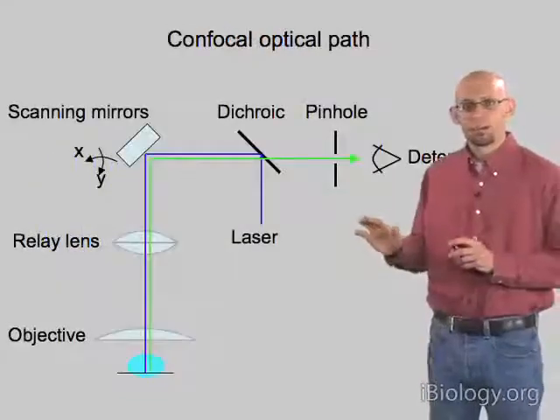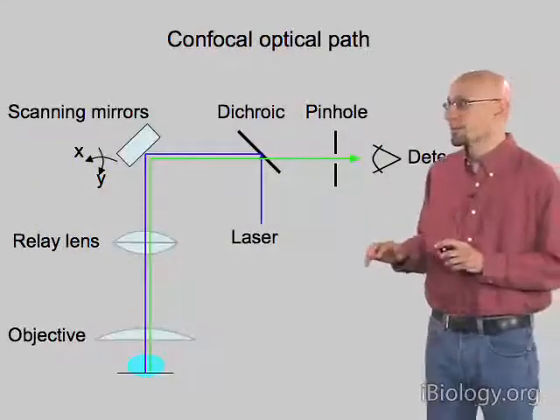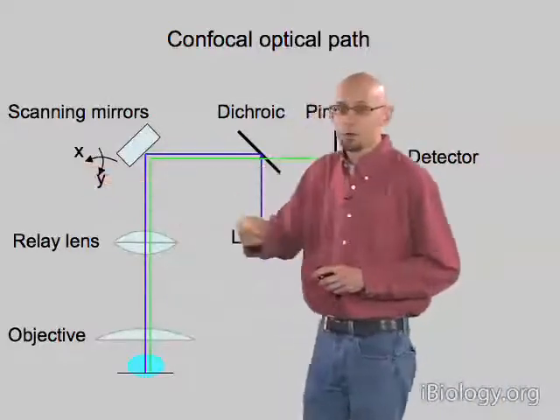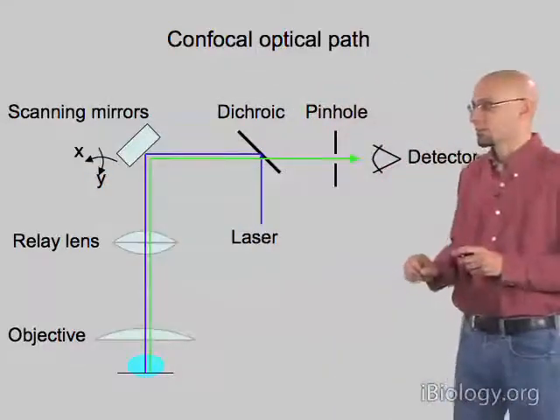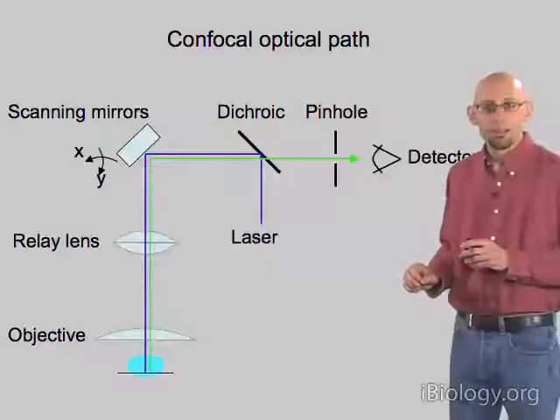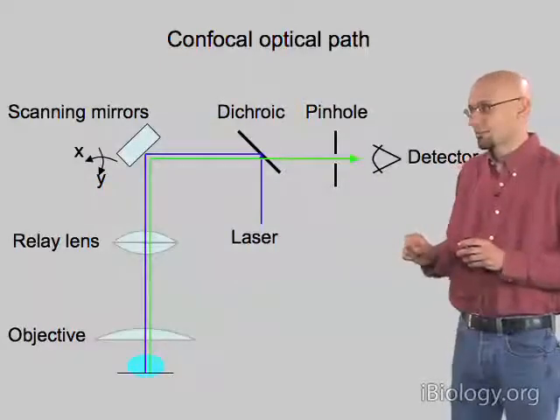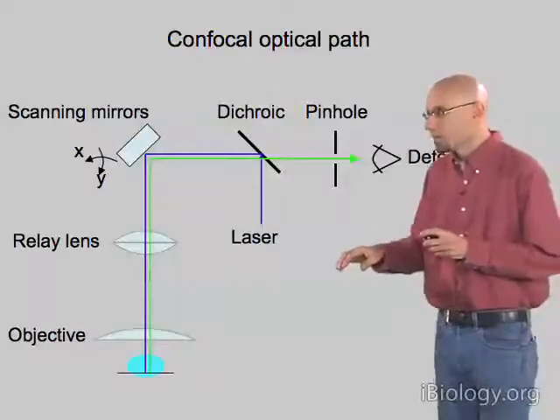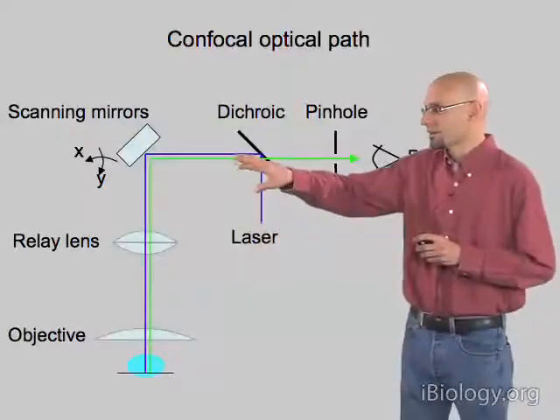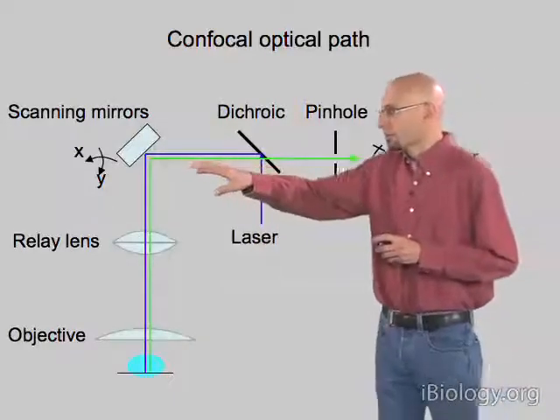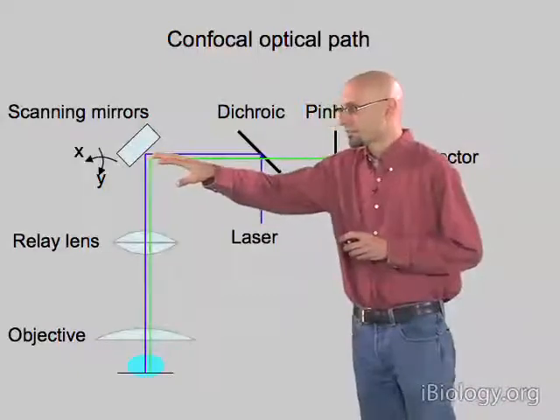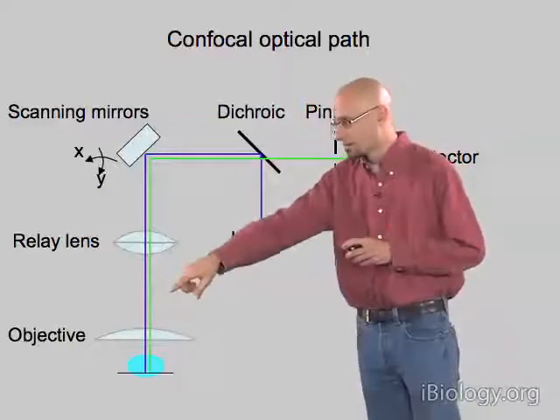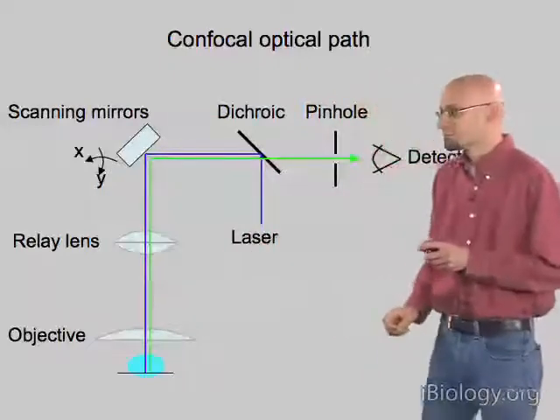Here's the optical path of the confocal microscope that allows us to do this scanning. The heart of it is this set of scanning mirrors, which allow us to rotate the angle at which the laser beam enters the objective, and thereby move the spot across the field of view, across our sample. We have a laser that enters our microscope, it's scanned by these scanning mirrors, which changes its angle so that once it's focused by the objective, the spot it illuminates in our sample changes.